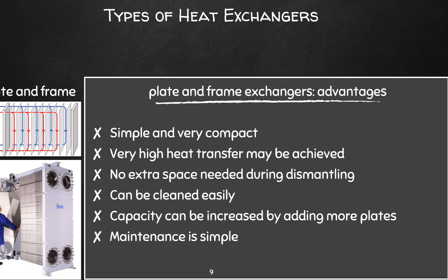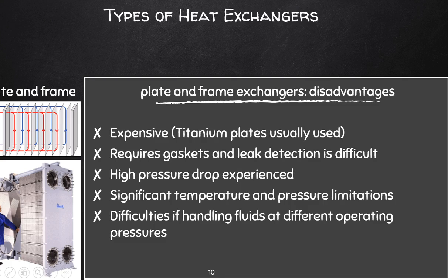They can also be modified quite easily because of this, because the frame tends to be much longer than the space that the plates take up when they are stacked and pressed together. So you can add more plates if need be, and add more gaskets as well.